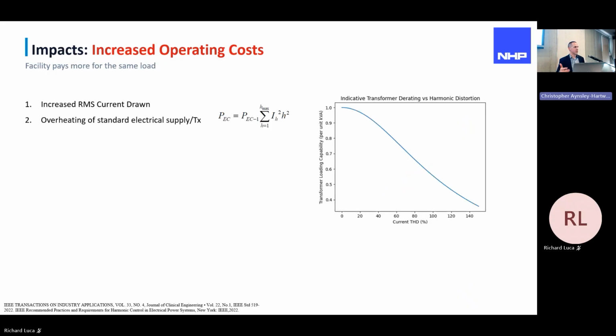Overheating of the standard transformer supply. So with transformers, in their makeup, the metal construction, the iron and copper losses, with increasing THD, these things need to be derated. So a 1000 kVA transformer may be only acting like a 700 kVA system.